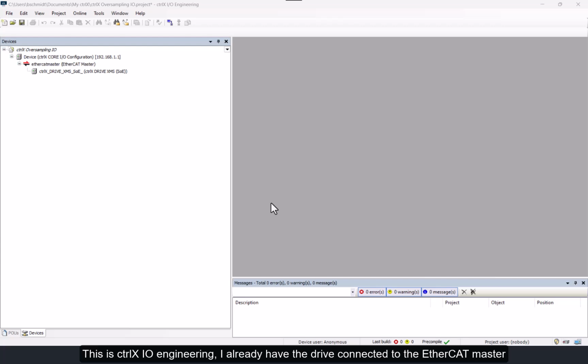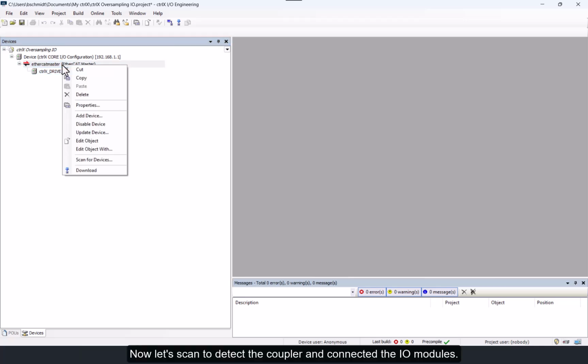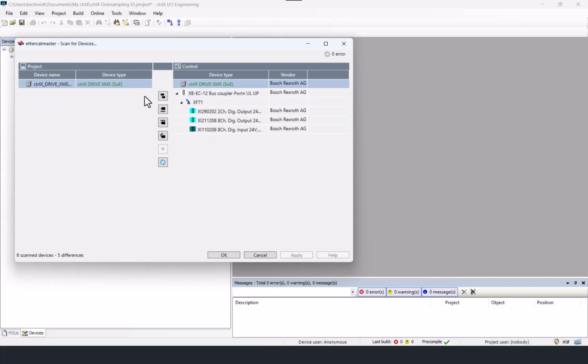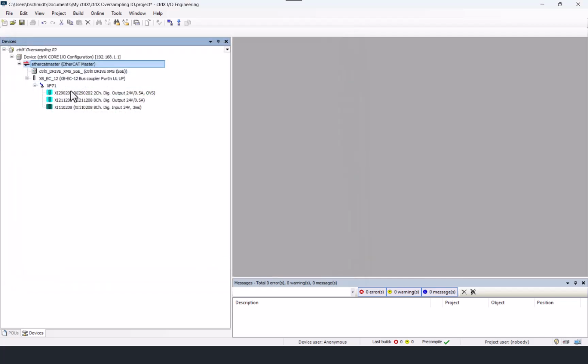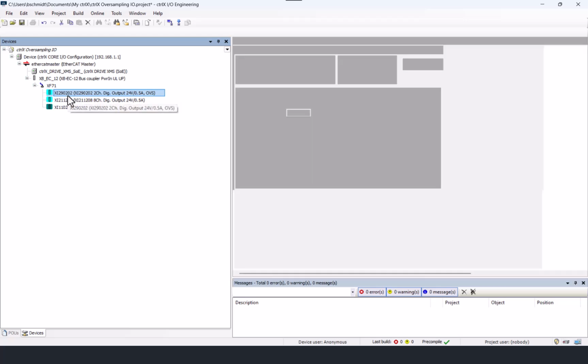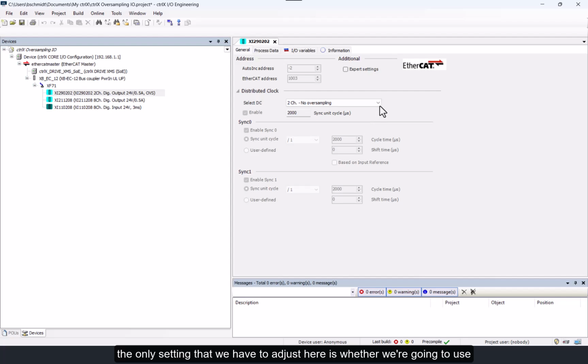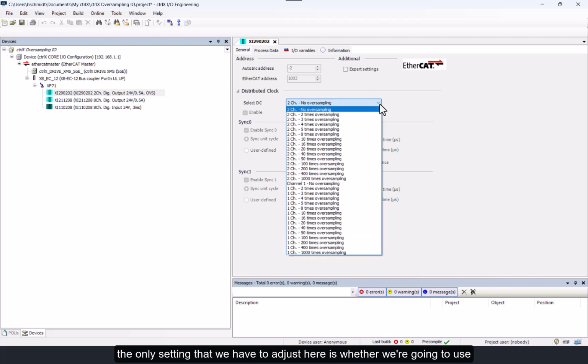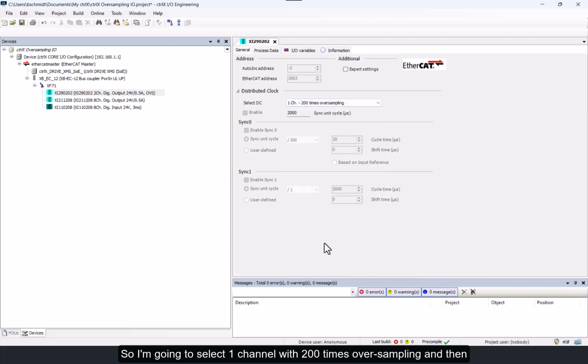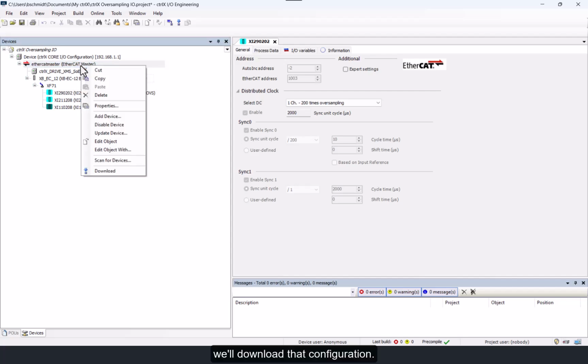This is ctrlX I/O Engineering. I already have the drive connected to the EtherCAT master. Now let's scan to detect the coupler and connected I/O modules. It sees them. The only setting that we have to adjust here is whether we're going to use 1 or 2 channels and specify the depth of oversampling. So I'm going to select 1 channel with 200 times oversampling. And then we'll download that configuration.